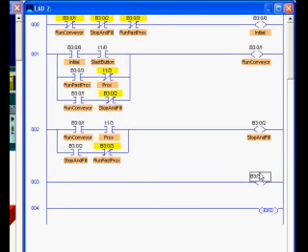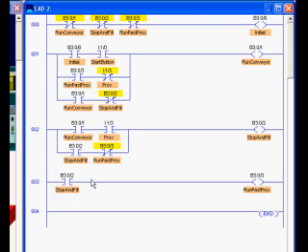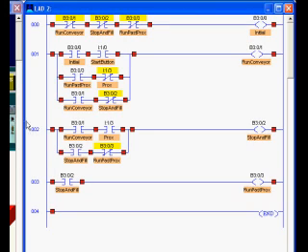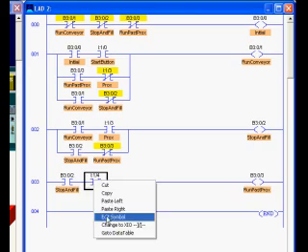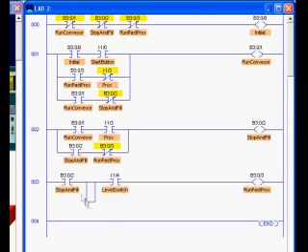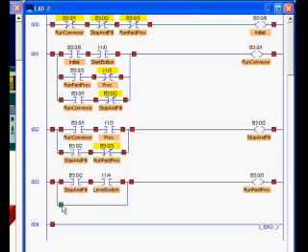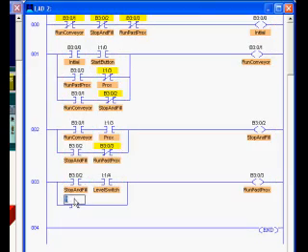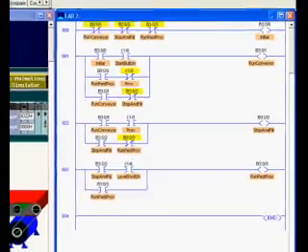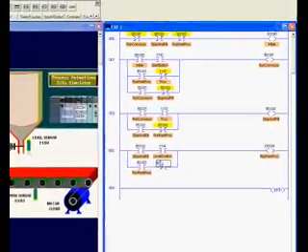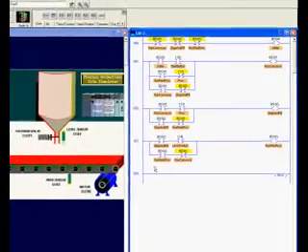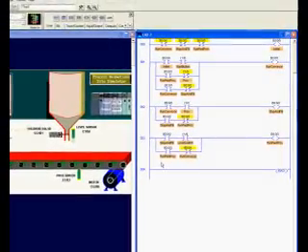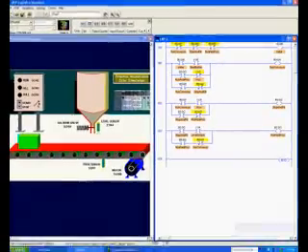So now let's do our last step B3:3. Once again where do we come from? We come from B3:2 so we'll put normally open. What condition makes us move to B3:3 that's the level switch. So let's put in the address of the level switch. Now after the level switch goes in there now let's add a branch. This is our latching branch because there are no more arrows coming into this. So now we're going to put in the B3:3 which is our latching bit and we're going to say where can we go from here. And it goes to B3:1. So that's the normally closed contacts. And there we have quickly built the states.